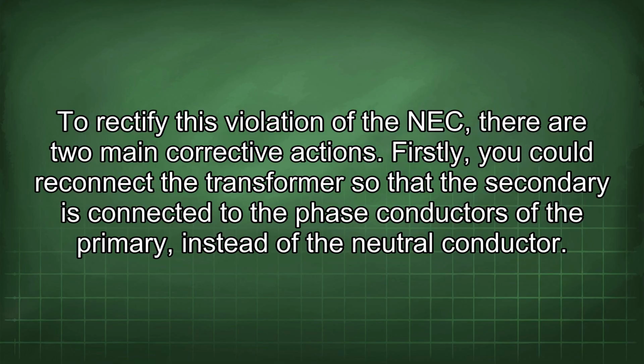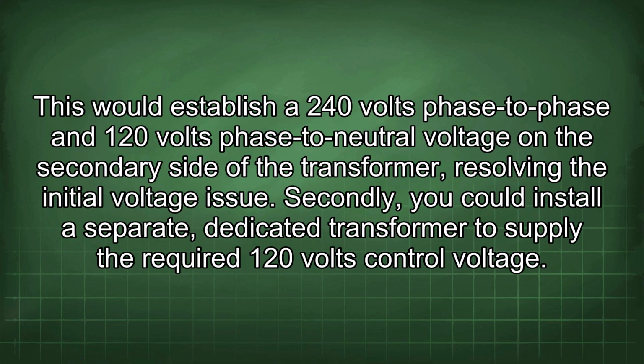Firstly, you could reconnect the transformer so that the secondary is connected to the phase conductors of the primary instead of the neutral conductor. This would establish a 240 volts phase to phase and 120 volts phase to neutral voltage on the secondary side of the transformer, resolving the initial voltage issue.